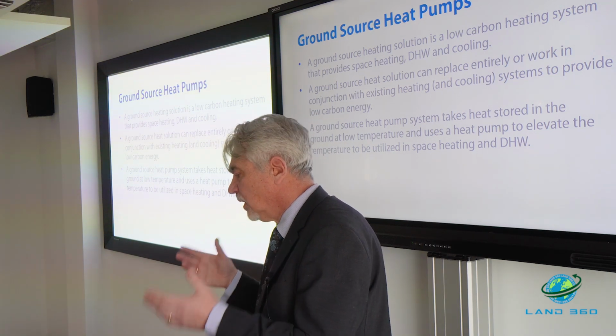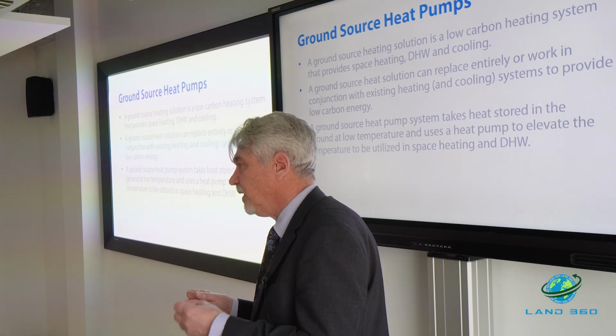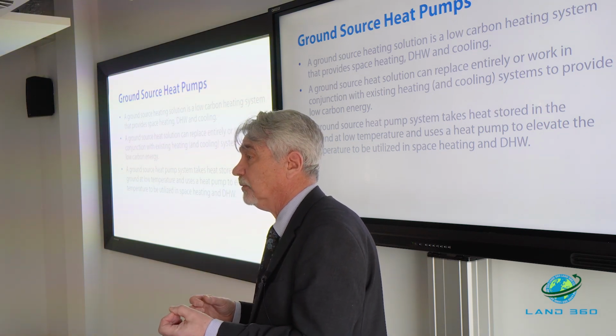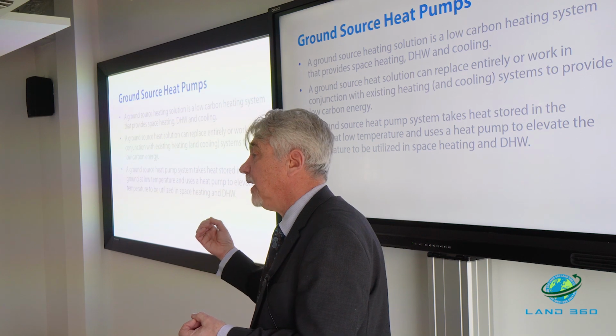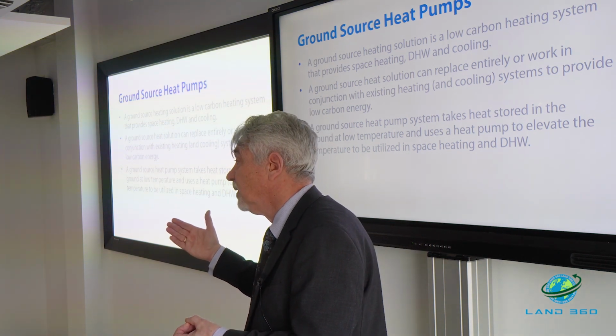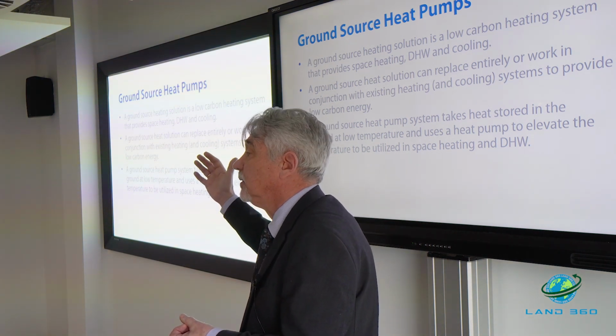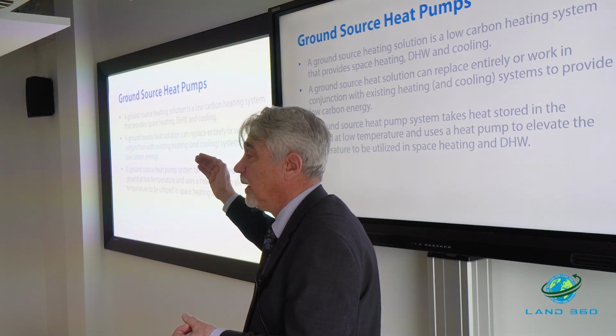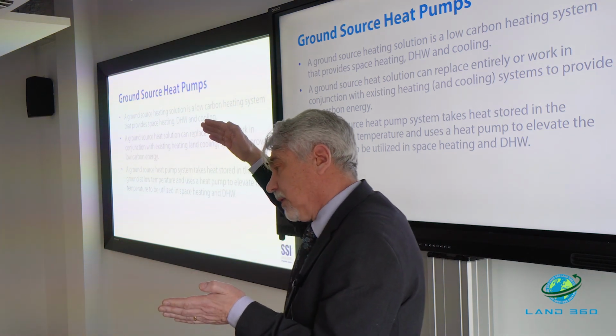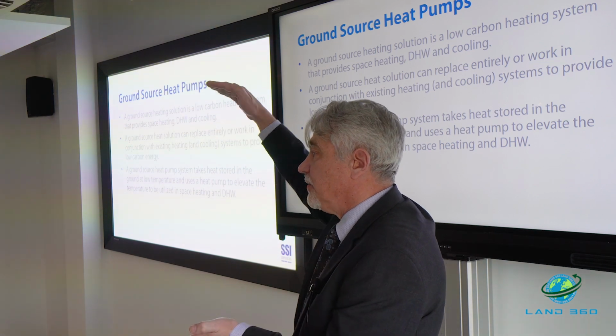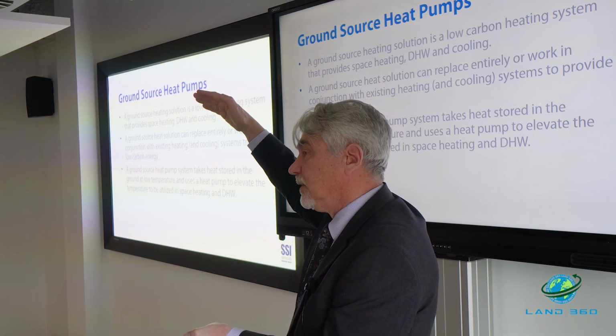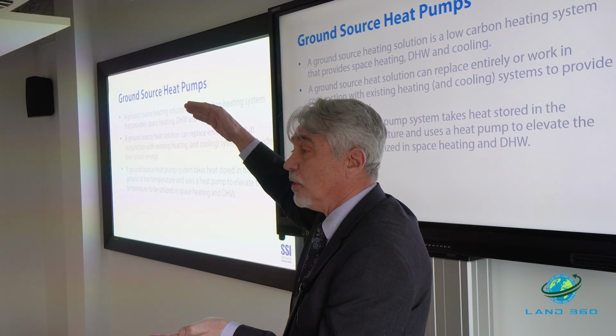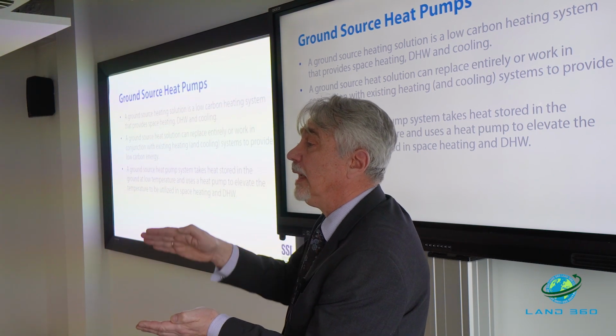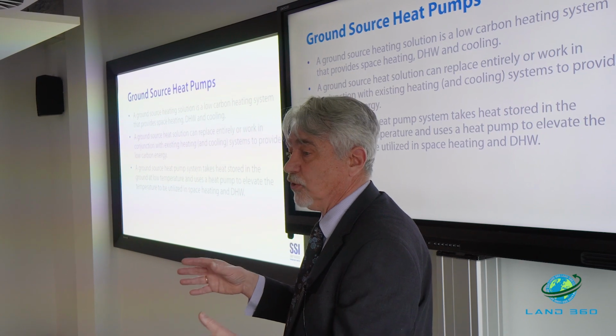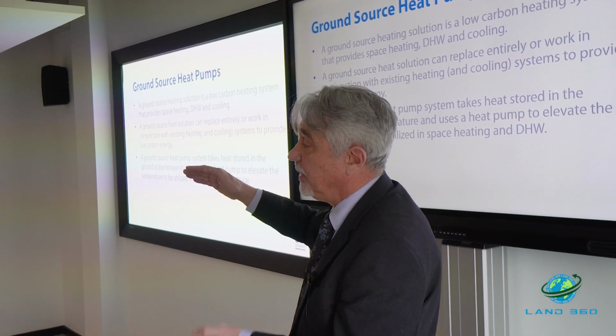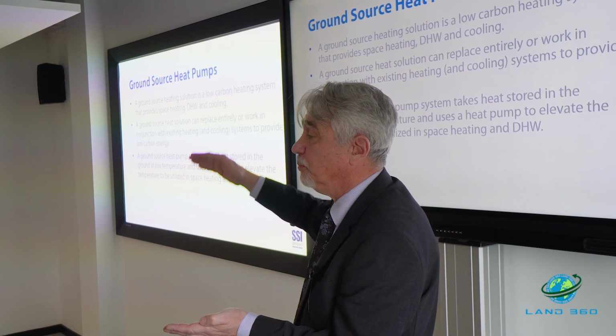So for the ground temperatures, drop a borehole into the ground about 150 metres, you'll get 10 degrees out of that all year round. And then we can use a heat pump to deliver that from 45 degrees up to 75 degrees. Heat pumps can do 75 degrees quite easily. The only thing is, those two temperatures are like this, so you've got 10 degrees here and 75 up here, and the distance they are apart shows you how efficient the system will be. So the closer you can get them together, the more efficient the system is. So you can't do much about this, but you're always trying to lower this temperature as best you can.